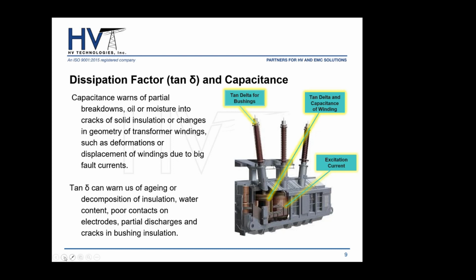And then when we talk about dissipation factor or tan delta, this allows us to gauge the aging or decomposition of the insulation. It can warn us about water content in your insulation, poor contacts on your conductors or electrodes. It can also warn us of partial discharges that may be occurring within your insulation system, and cracks in a bushing insulation, for example. So for the transformer, which is a very typical application, you can do your tan delta measurement for your bushing as well as your winding, and you can also do capacitance on your winding. And this instrument will also let you do measurement of excitation current.